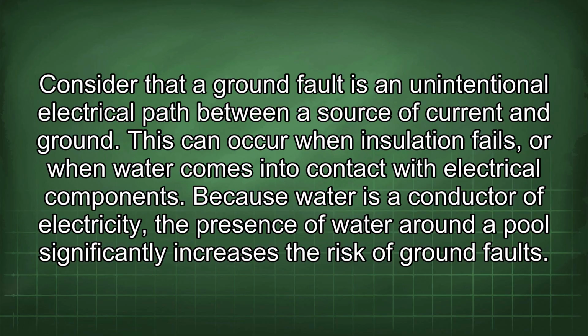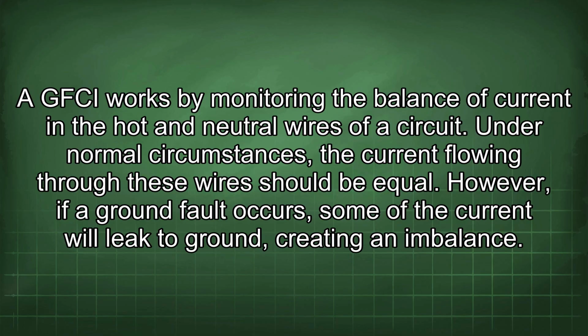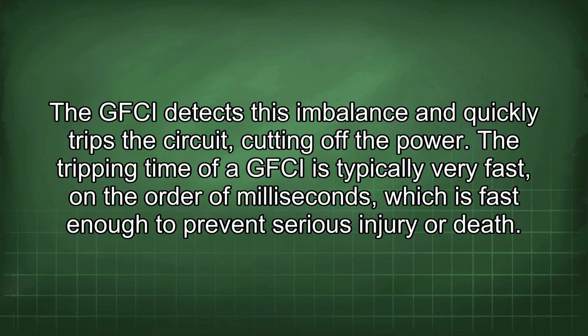Consider that a ground fault is an unintentional electrical path between a source of current and ground. This can occur when insulation fails, or when water comes into contact with electrical components. Because water is a conductor of electricity, the presence of water around a pool significantly increases the risk of ground faults. A GFCI works by monitoring the balance of current in the hot and neutral wires of a circuit. Under normal circumstances, the current flowing through these wires should be equal. However, if a ground fault occurs, some of the current will leak to ground, creating an imbalance. The GFCI detects this imbalance and quickly trips the circuit, cutting off the power.